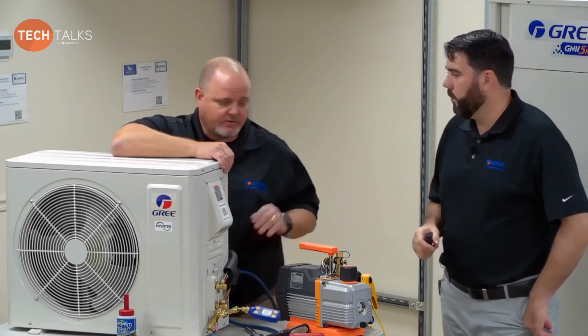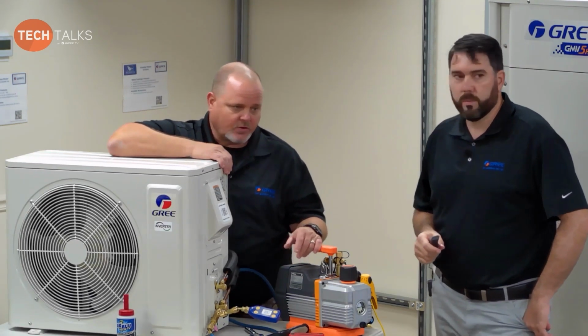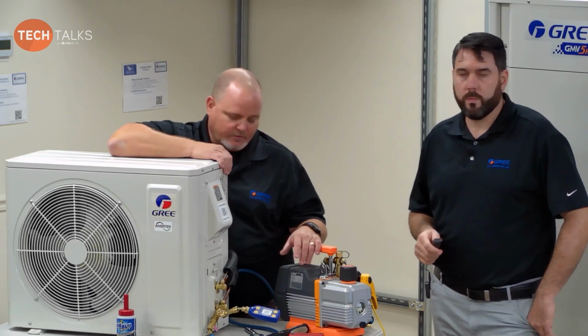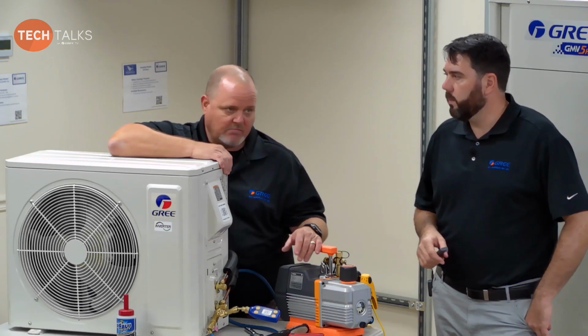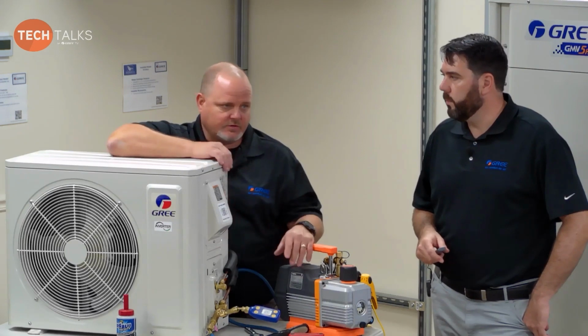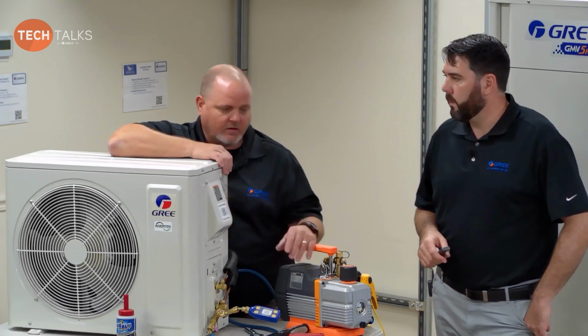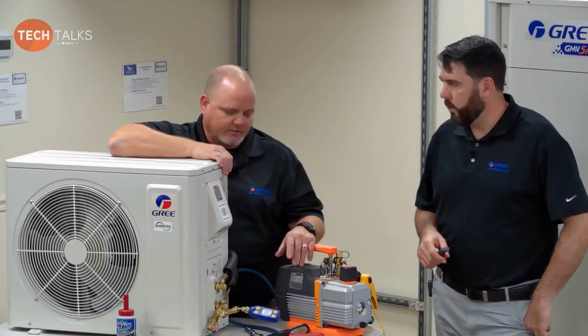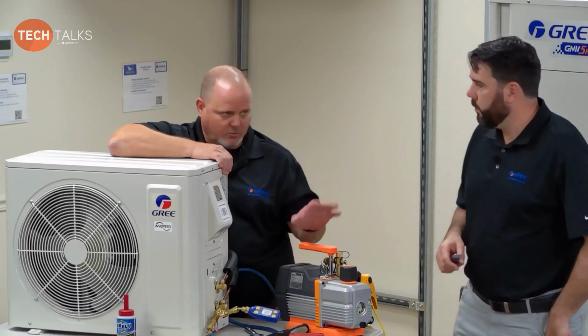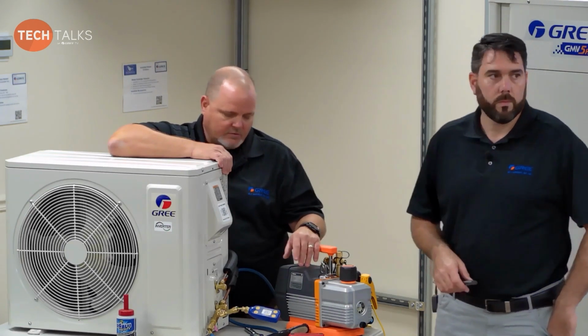Again, that's going to be a big difference as to whether we're pulling down just a coil and a line set on a new installation. You're going to hold vacuum on that better than if we're servicing this unit and we're having to pull down compressor, accumulator, and everything else. That's a whole other story, which we will be talking more thoroughly about when we talk about the evacuation process.